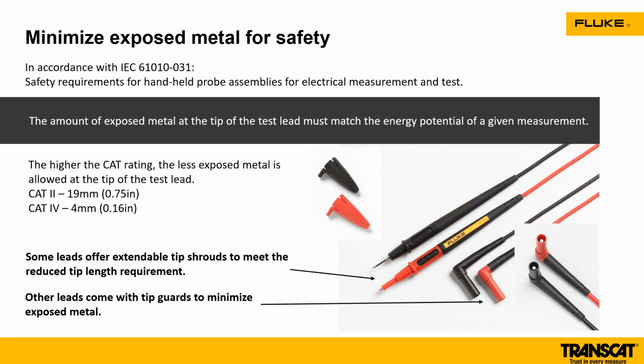You can even see the design changes in the IEC. No longer do we have exposed ends that even go into the inputs of our meter. They're now shrouded. It's all about safety out there in the field. What if your test lead came out as you were touching metal? You touch that, now you're shocked. So again, a key win, all part of that IEC 61010 standard.